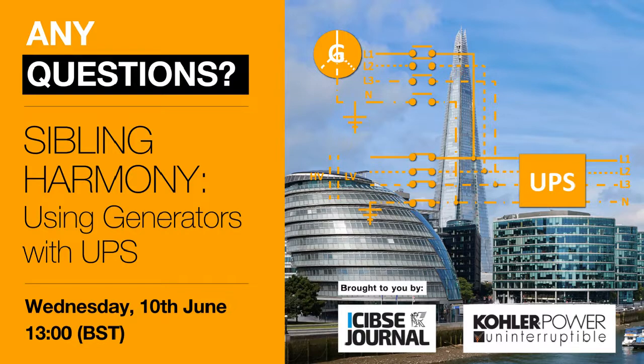Got a question from Zia here, and Zia asks, what can be the negative consequences of using an automatic mains failure panel, an AMF, or is it absolutely necessary? Okay. An AMF panel is an automatic mains fail panel. Strictly speaking, not absolutely necessary, but it means if the mains fails, someone has to go and start the generator and do a manual changeover. So nowadays that's typically not acceptable. So I wouldn't want to say it's absolutely necessary, but it's highly recommended.